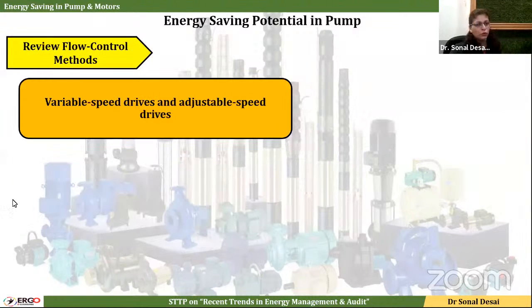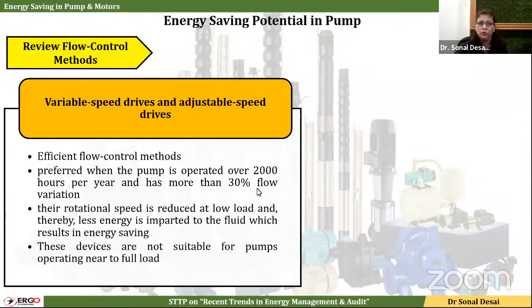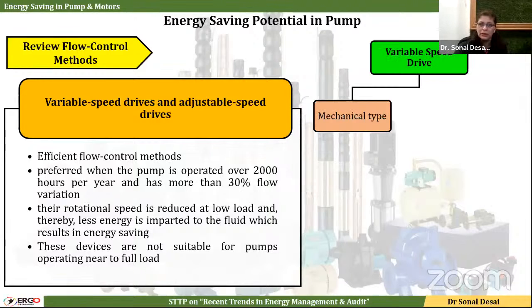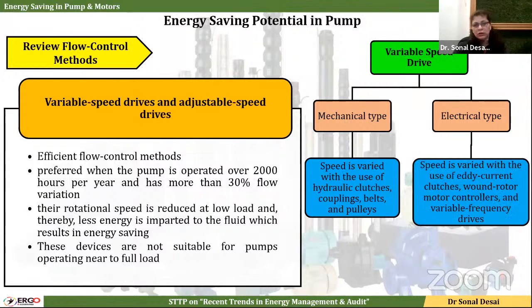Go with a variable speed drive. It is an energy efficient flow control method. It is used whenever a pump is operated for 2000 hours or more, or a 30% or more flow variation is there. You are supposed to remember this to implement it whenever you come across such opportunities. So either mechanically or electronically the speed will be reduced, and they always have a good payback. So go for it. Speed variation in a mechanical one can be based on clutch, belt or pulley, or in case of an electrical one, it can be based on eddy current or a wound-rotor type of arrangement.